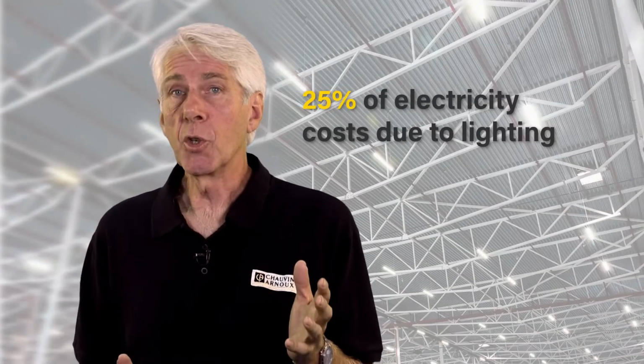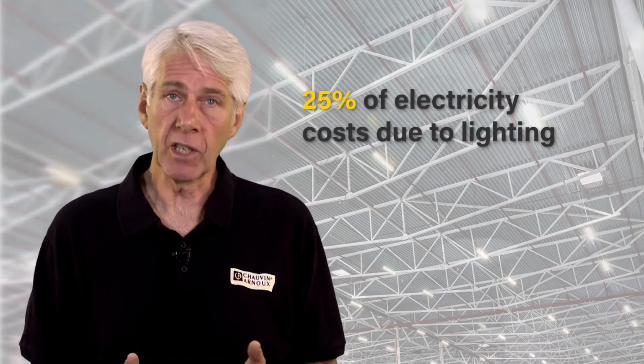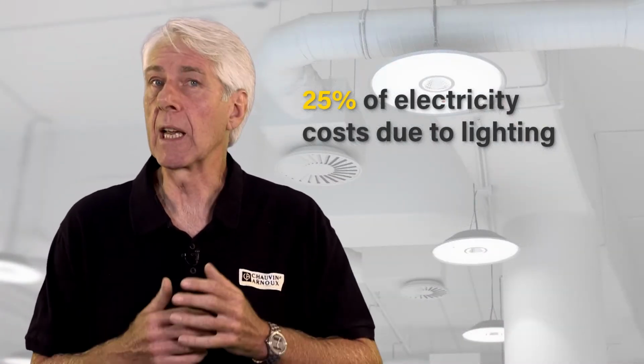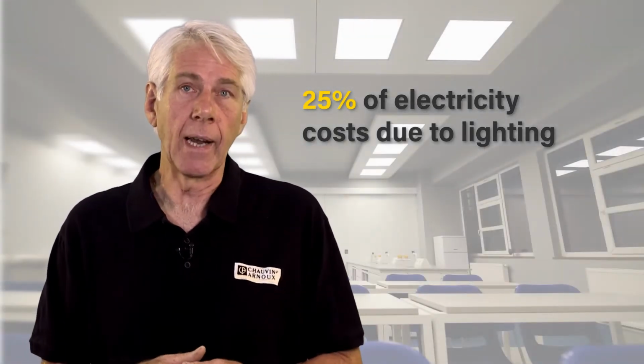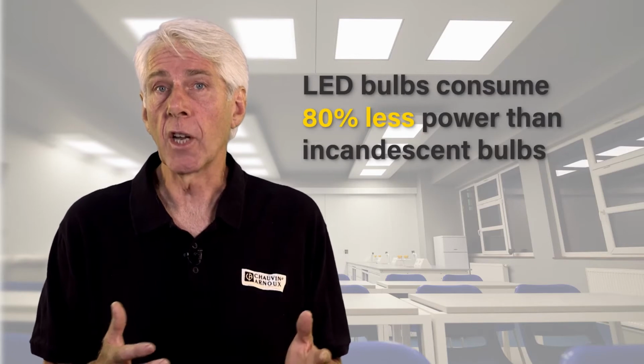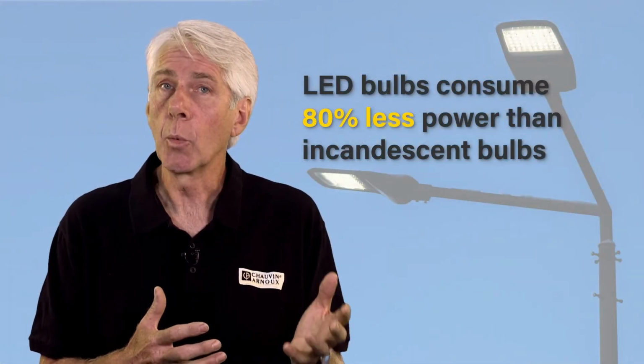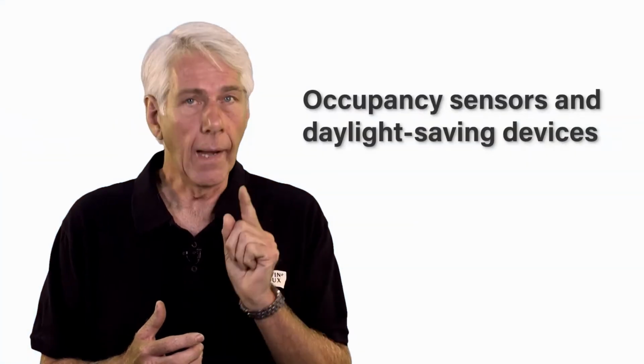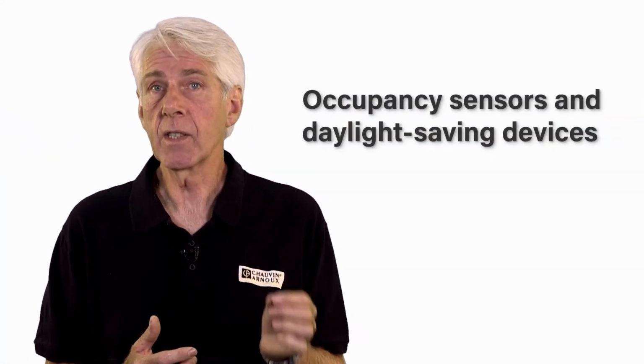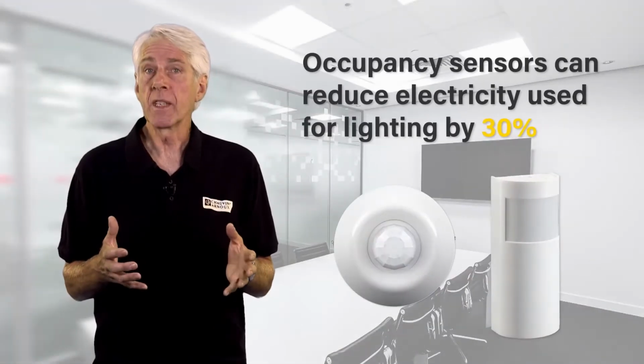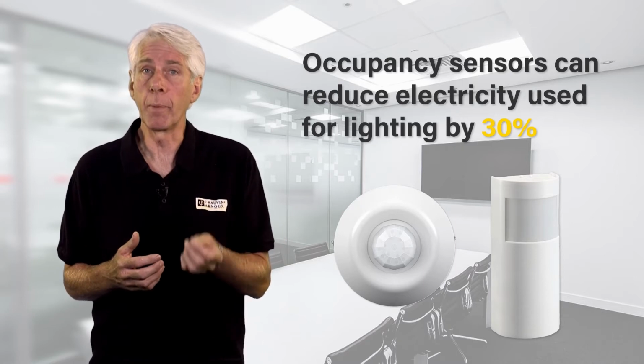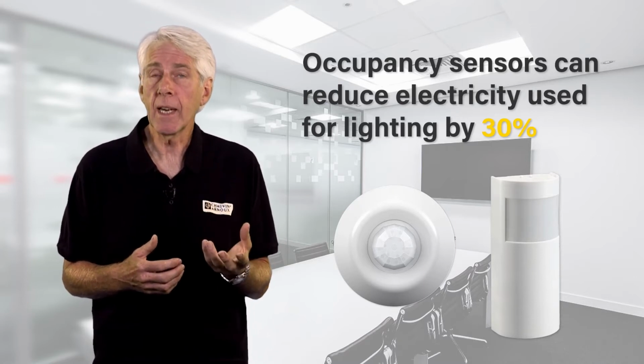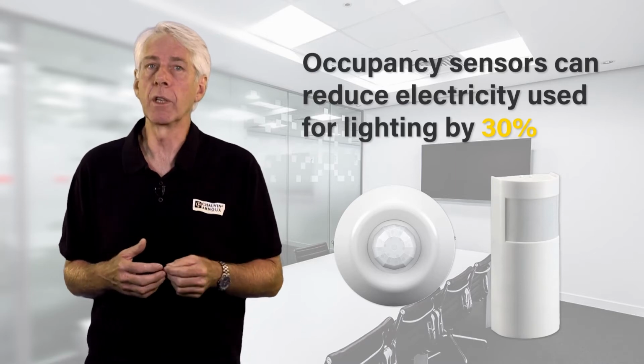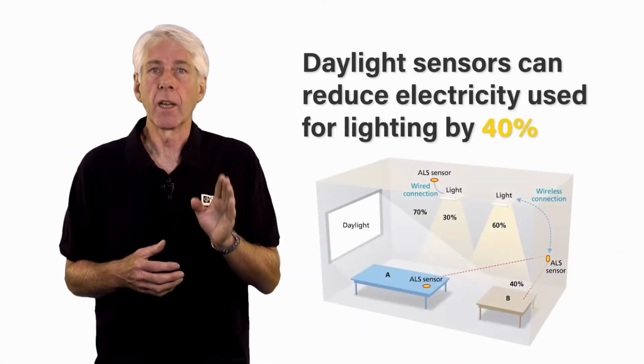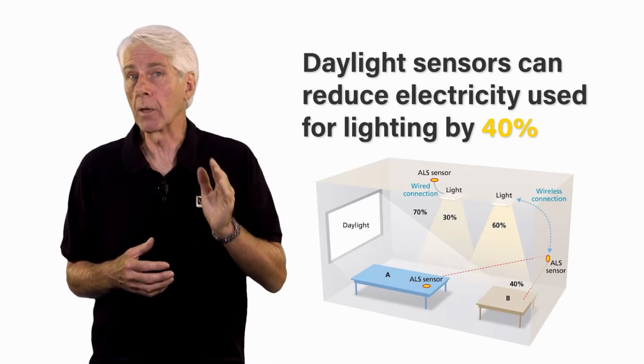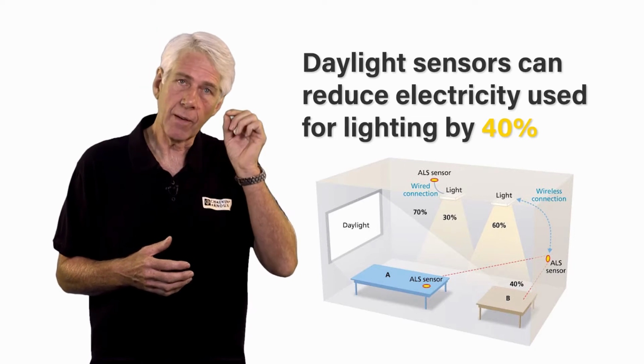With lighting contributing to 25% of the average industrial facility electricity bill, and with office buildings and call centres using even more, the efficiency of lighting equipment and its use is vital. Obvious changes are to move from incandescent lamps to LED, with savings of up to 80%. Less obvious are the effective use of occupancy sensors and daylight saving devices. Occupancy sensors in occasional rooms like meeting rooms, corridors and bathrooms can cut lighting costs by 30% by ensuring areas are only lit when they're in use. And with daylight sensors adjusting artificial light levels as the sun comes up and goes down during the working day, a business can save a further 40%.